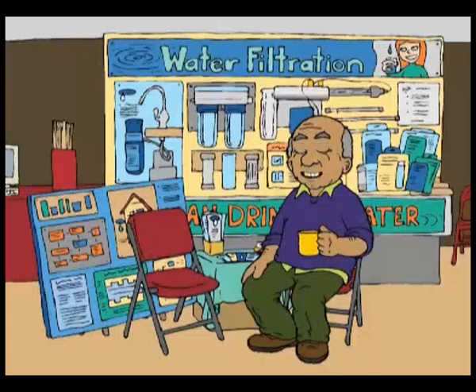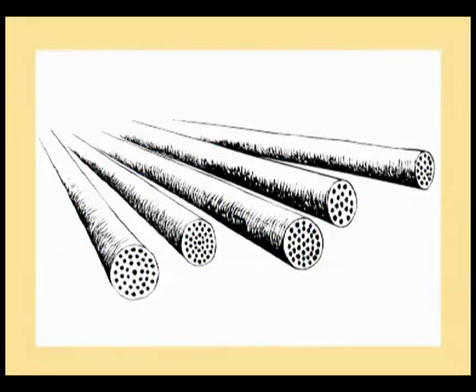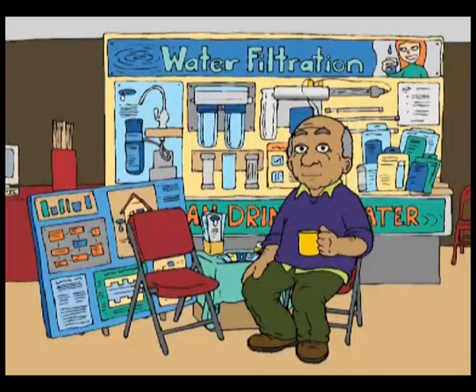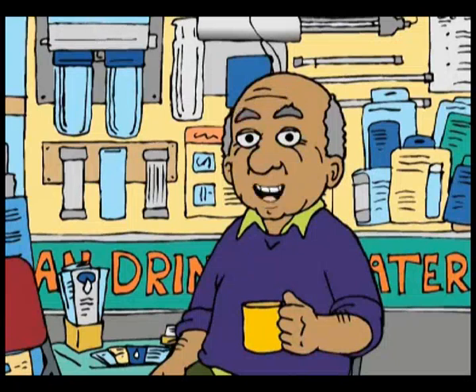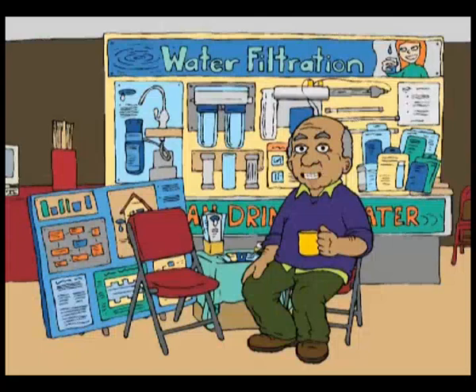Another type of filter that is becoming more widely used are membranes. They're pretty expensive but the price is coming down. Usually installed in large supplies, but some small supplies are starting to use them. Water flows down tiny straws only about a millimetre in diameter. The pores or holes in these straws are so small that even viruses can be filtered out. They do need to be cleaned carefully and from time to time with chemical cleaning solution. The water needs to be pretty clean before going through these membranes, so pre-settling is usually necessary. They're a pretty complex system, but we're going to see a lot more of them.